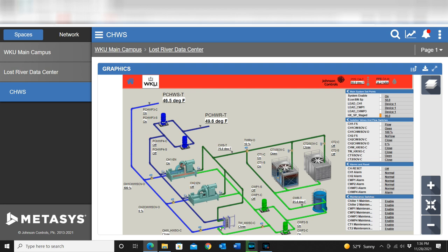If you do not isolate out the condenser water when you're running that higher set point on one side of this heat exchanger, and you don't isolate out this chilled water from this other side, you're basically going to be fighting yourself and reintroducing heat back into your chilled water, which is something you don't want to do in this type of a system.